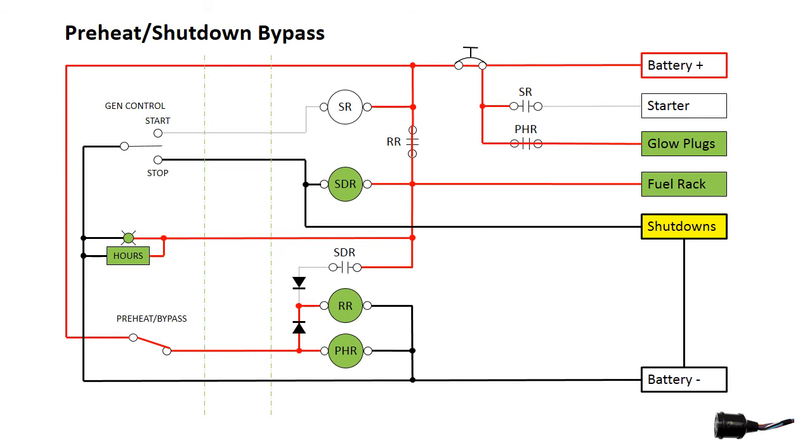Because the shutdown relay is energized, the normally closed contacts are now open and the run relay is not latched. Once we have adequately preheated the engine, we can crank the starter.